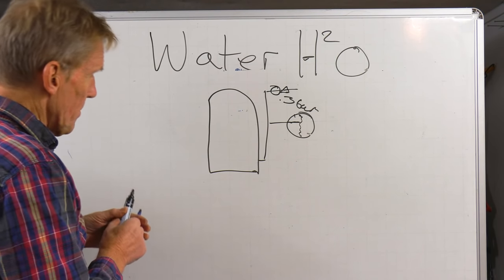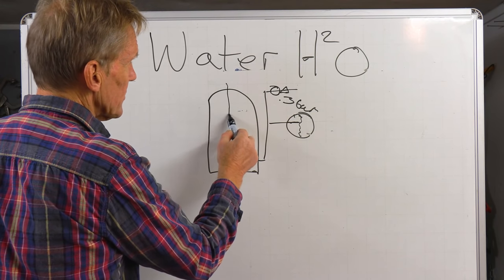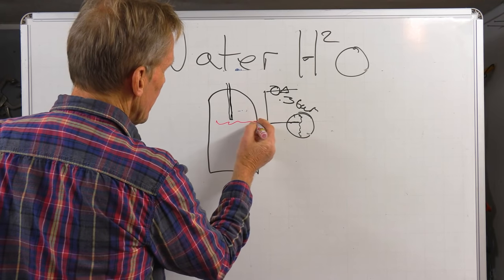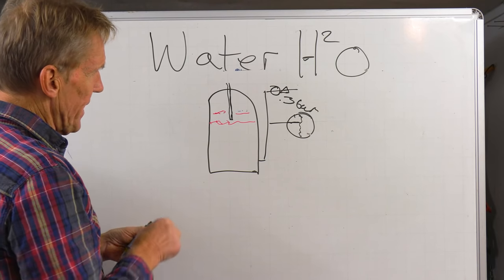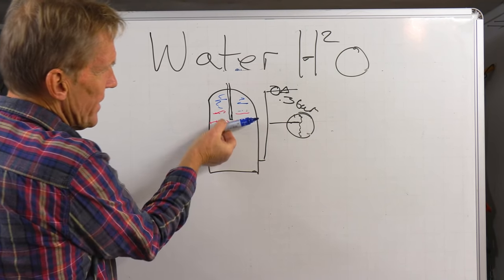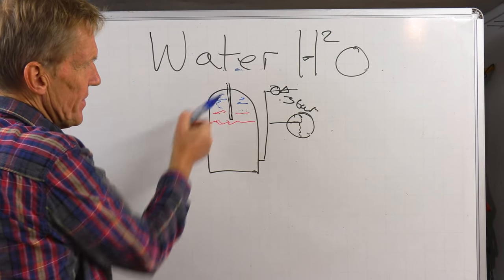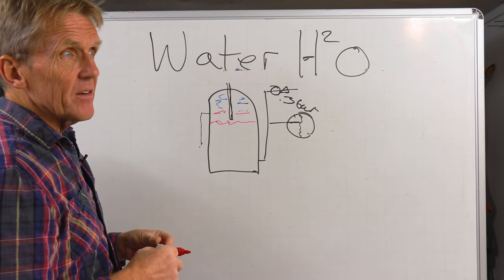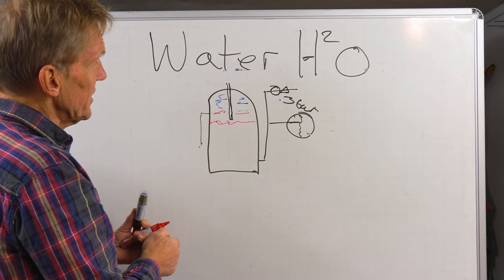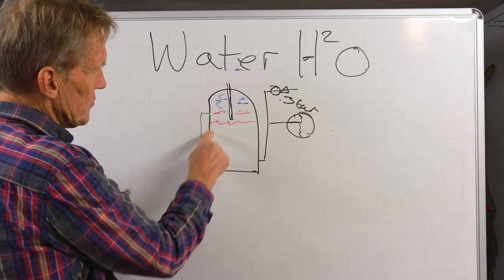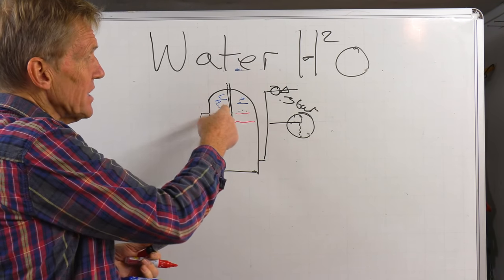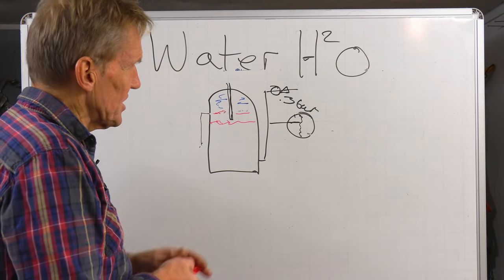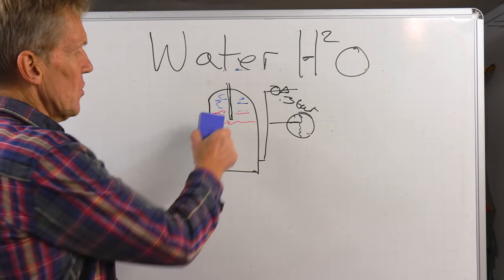As the water's heated up, it's not going to be 1,700 times, by the way, because we're not taking it to boiling point in steam, but it will expand. And we have to make sure that that expansion vessel is big enough to accommodate the amount of expansion that's taking place in that cylinder. Now, the other thing that you sometimes get is what we call a bubble top cylinder, which means that the pipe that's going up the cylinder comes down into the cylinder there. So it's taking the water from, so let's do this right, because then you get the hot water. There's the hot water. And the hot water's going up to about there, but that top bit there is just fresh air. So that one is where the expansion takes place inside the cylinder. It's got up and down, up and down. Now in the end, those bubbles get displaced. And so what we have to do is we have to drain the cylinder down on the expansion and temperature relief valve, which is on the side. We drain that cylinder down to the point where the water drops to below. So once that stops running, we know the water levels drop to below and that will replenish, so long as we've got a hot tap open, by the way, that will replenish the air inside that cylinder and give us another three months, six months, or maybe even a year. But that's one of the things that is done on a service call. If you've got a bubble top cylinder, they make sure that the air bubble is replenished.